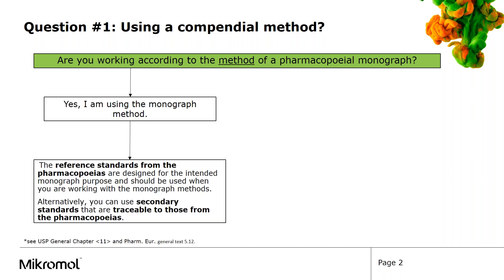If you are using the monograph method, the best choice would be the reference standard from the corresponding pharmacopoeia, because it is designed for that special use. Alternatively, you can use a secondary reference standard that has been established by comparison to the pharmacopoeia reference standard.